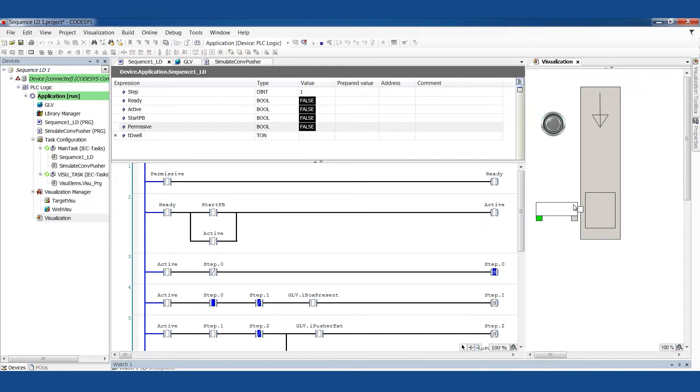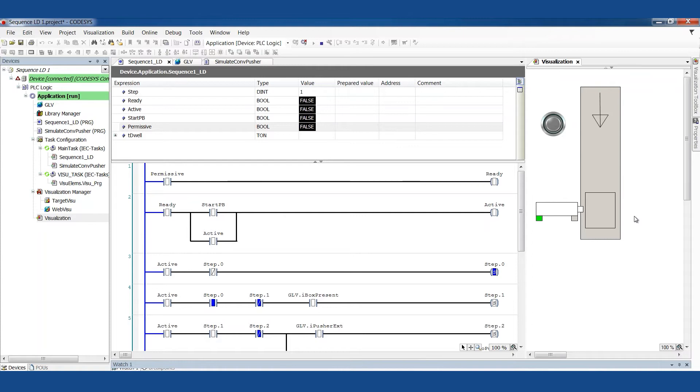I have a pretend sensor in this simulation. I also have a pusher device. Boxes are coming down the conveyor, and when they get here, when they trigger that sensor, we want this pusher device to push that box off onto the next step in the process. The pusher will have two outputs, one to extend and one to retract, and it also has two inputs that tell us where the cylinder is.